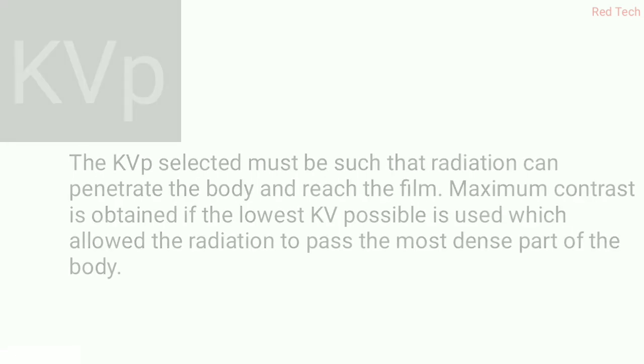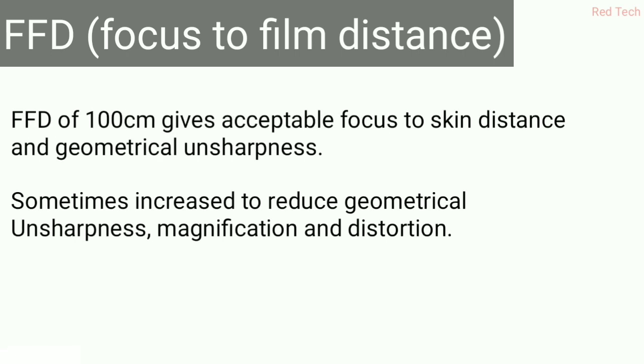Next is FFD — focus to film distance. In radiography, 100 centimeters is the standard acceptable focus-to-film distance. To reduce geometrical unsharpness, magnification, and distortion, we can sometimes increase the distance beyond 100 centimeters depending on the case.